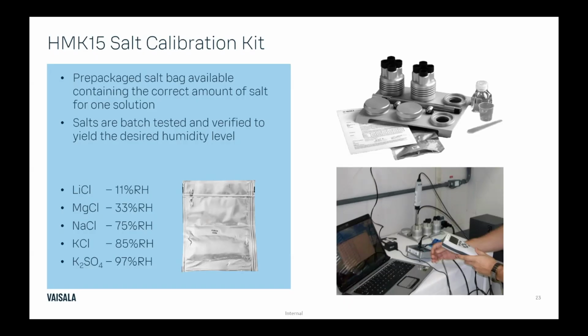The reason we recommend keeping a portable on hand is that while we expect these to be exactly 11% or exactly 75%, a lot of times when you mix them with the water and they're sitting in the chamber, it's not a controlled environment out in the field, so you'll get an 11.1, 11.3% reading, or maybe even a 75 or 74.9, something like that. So having that reference meter offers you a traceable accuracy level, so you can adjust to that 74.9 or that 11.3 instead of just adjusting to that 11%. So it makes your calibrations and adjustments a little bit more accurate.